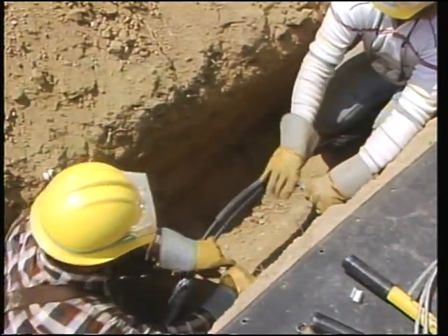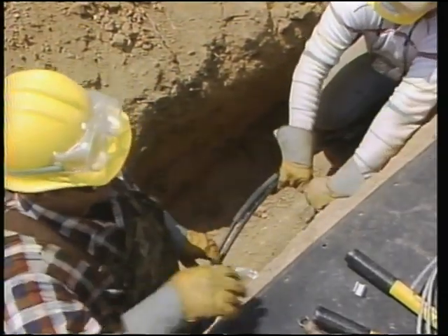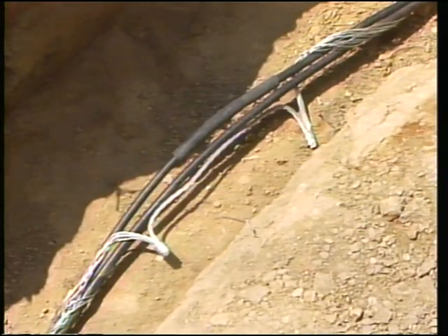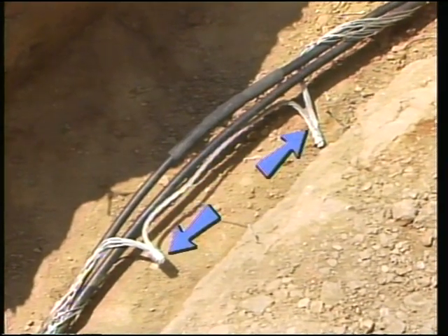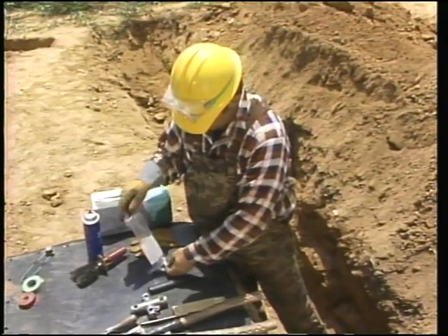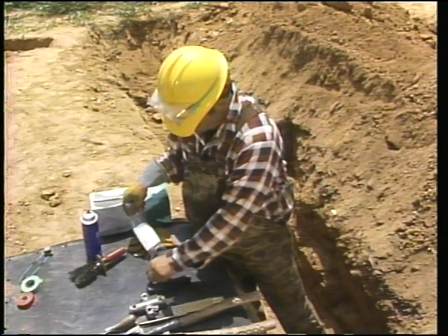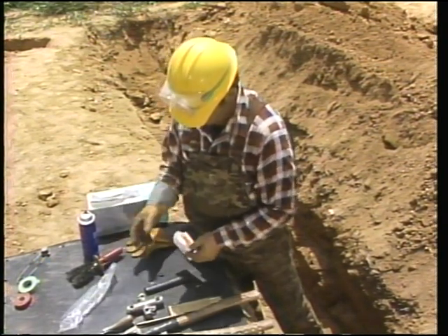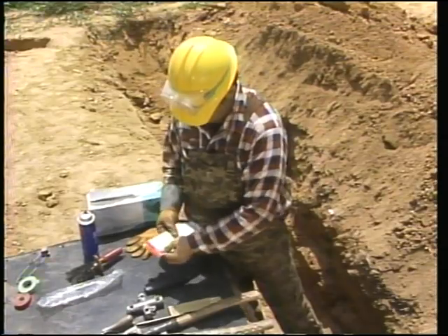Now, on this particular secondary cable, there is a concentric neutral layer. To complete the job, after the connector splice is made, the workman must reconnect the concentric wires, as we've seen before. Now, the last type of splice we'll look at is the rolling ring seal splice. The rolling ring seal uses rubber O-rings and an insulating tube.